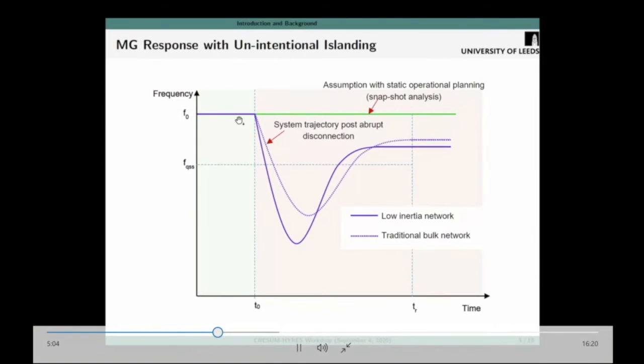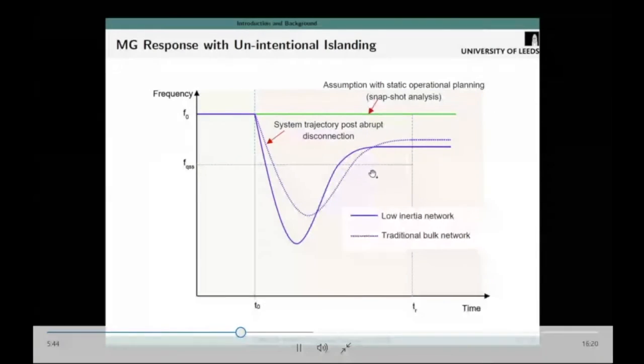However, as we can see, when we have an islanding event at time t0, there is a high rate of deterioration in the frequency, dipping to a given level, and after a steady state is attained that may be different from the pre-islanding steady state. We notice here that the frequency response of the low inertia networks that consist of mainly the fast acting converter units has a high rate and lower dip as compared to the traditional bulk networks, which have a slower response and a much shorter dip.